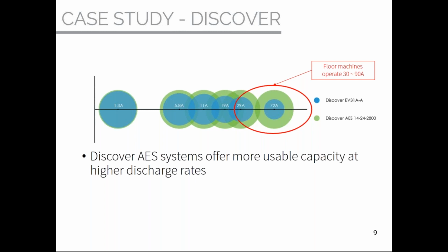This is really due to the internal efficiency of lead acid, typically only about 80%, whereas with lithium it's upwards of 95%. This graph summarizes the need to oversize your lead, because you should only use about 80% of its capacity to maintain a healthy lifetime, and you typically also need to oversize lead because of its low internal efficiency.